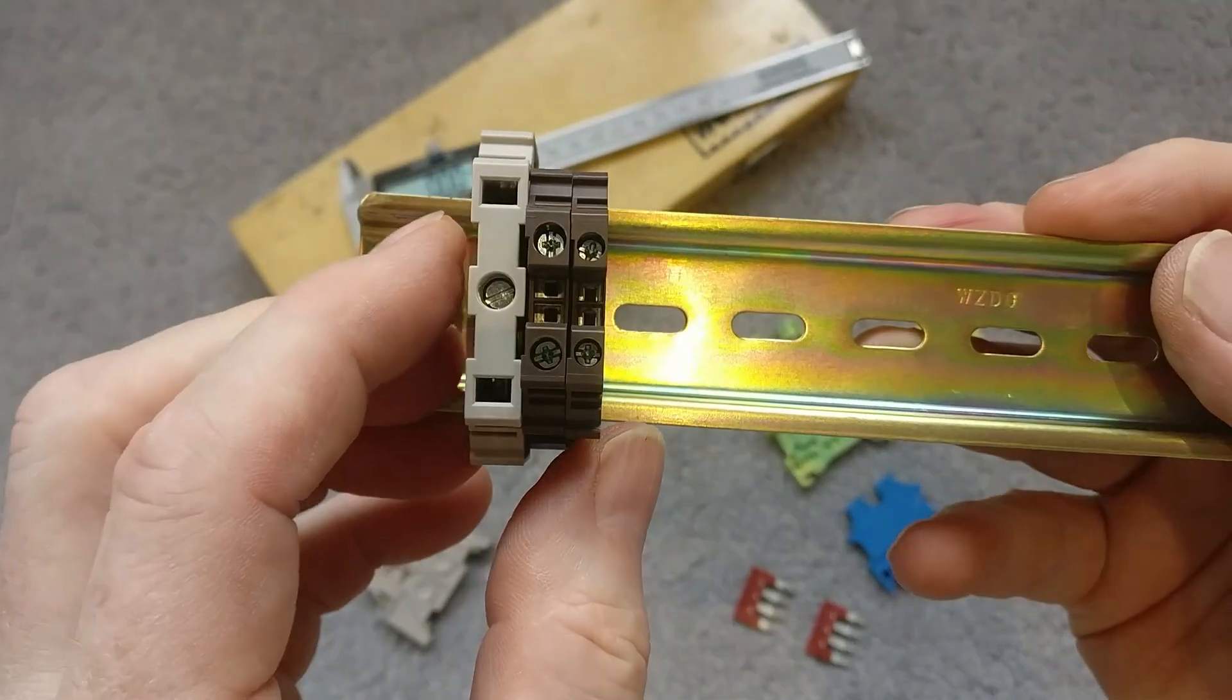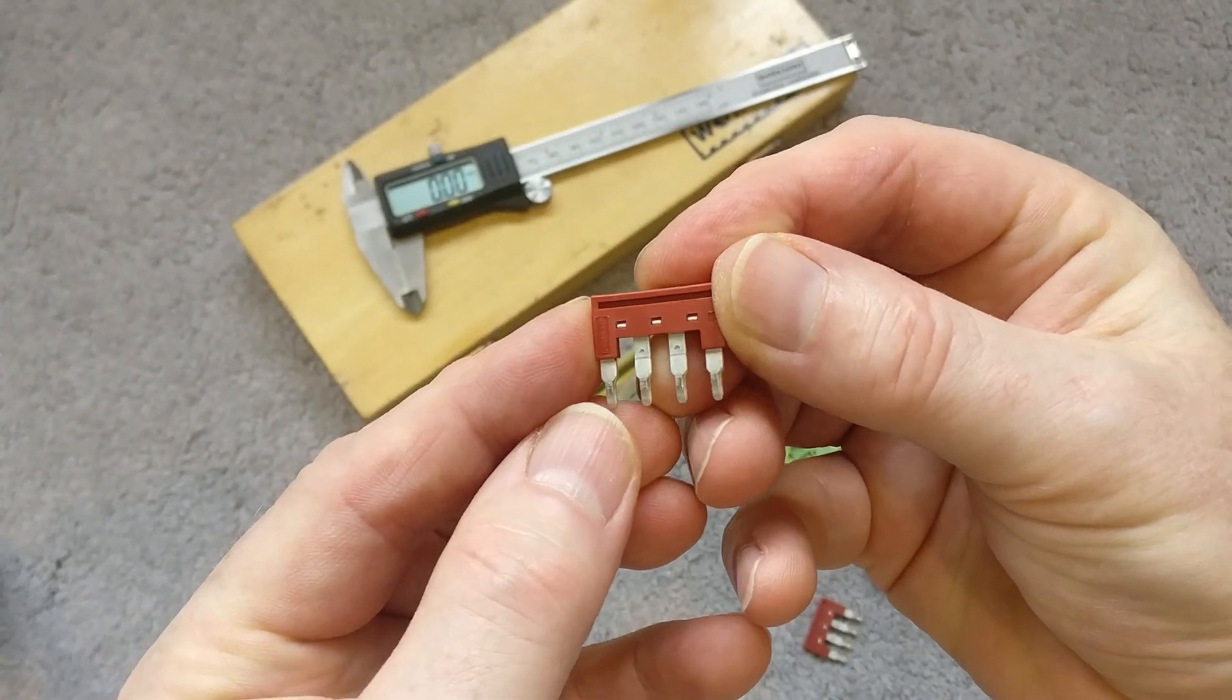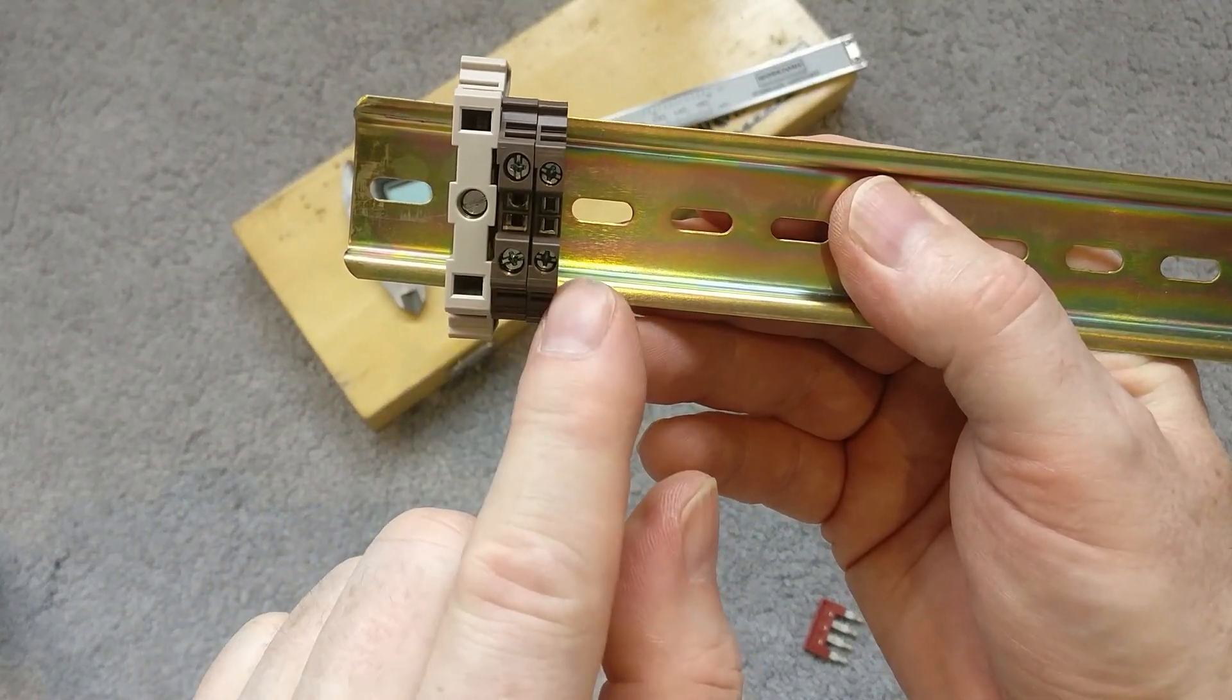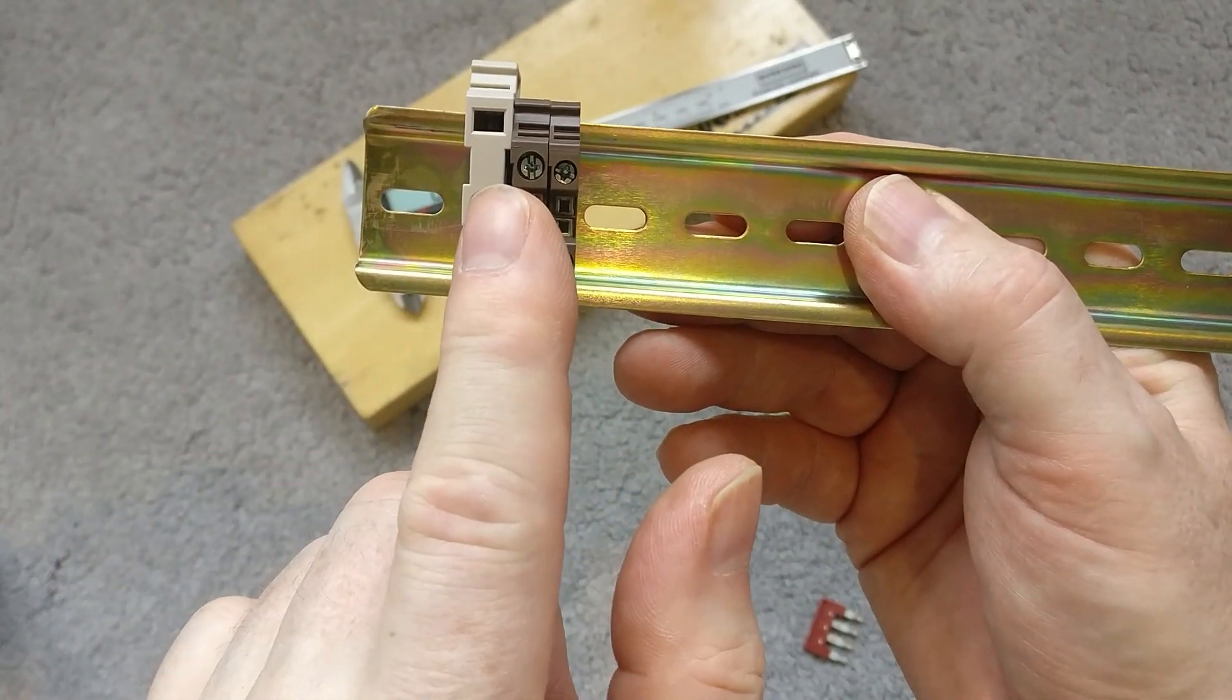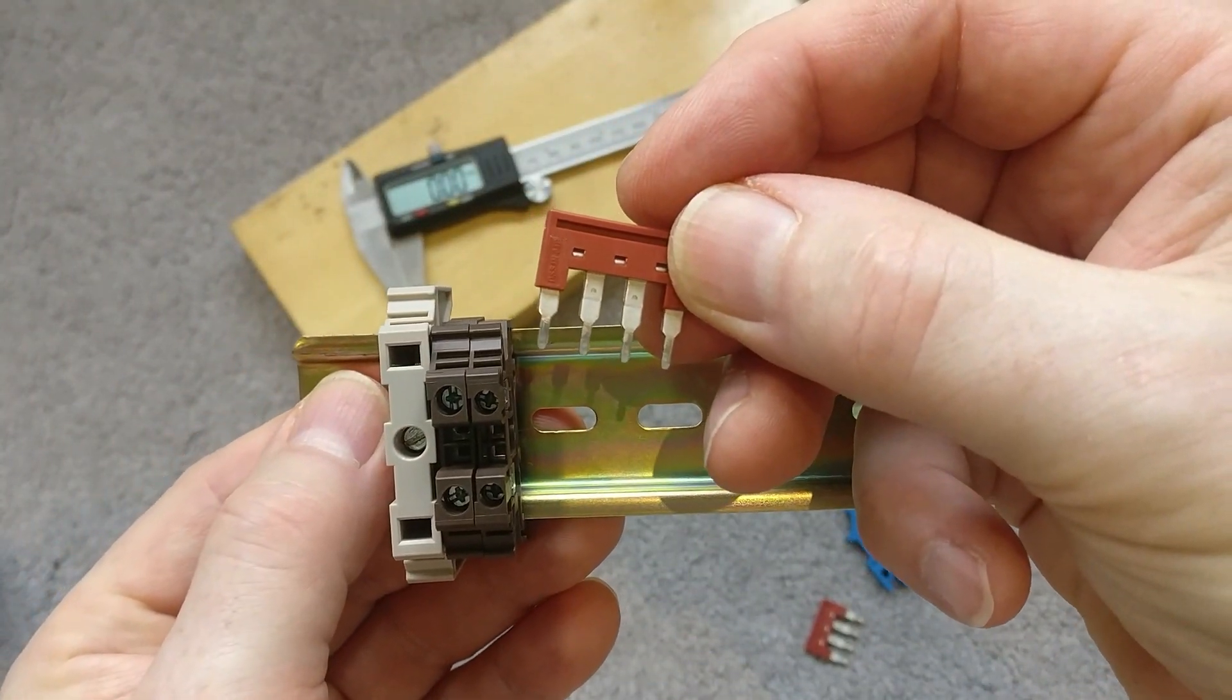And then you've also got these positive rails. So here you can see I've got two lives, they are physically separate. So the two wires that would come in and come out, they are physically separate from each other. If you wanted to have a common block of lives, then you can use these little connectors. They come in various lengths from twos and they just keep going up and up and up. And then you can link as many of these together as a daisy chain.